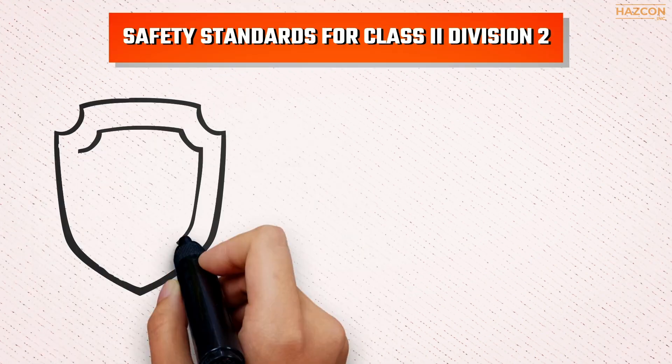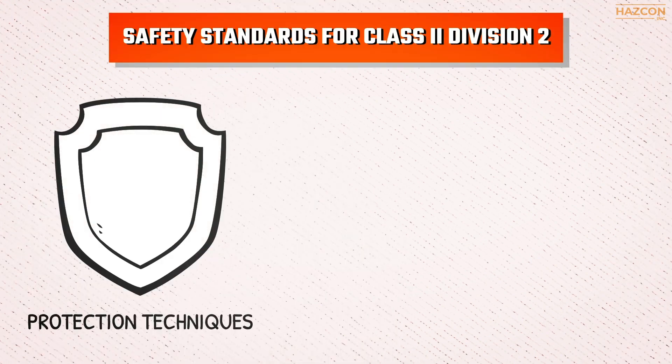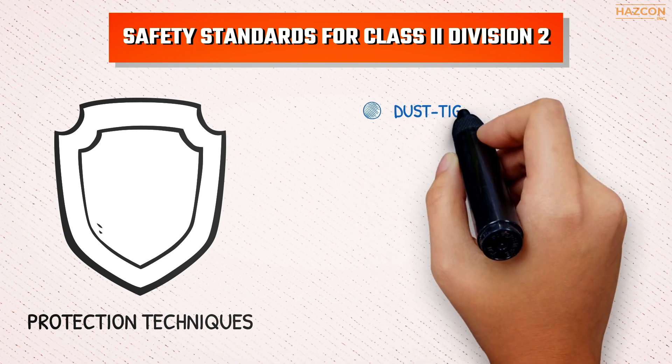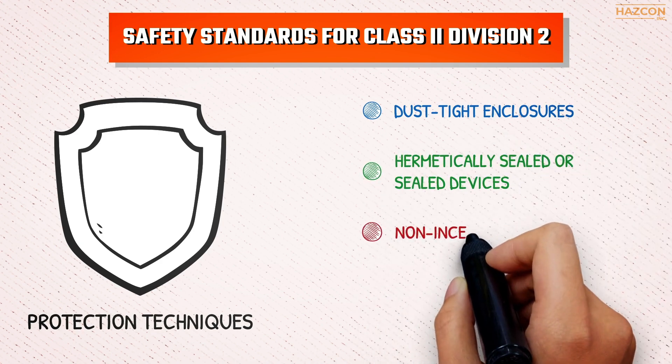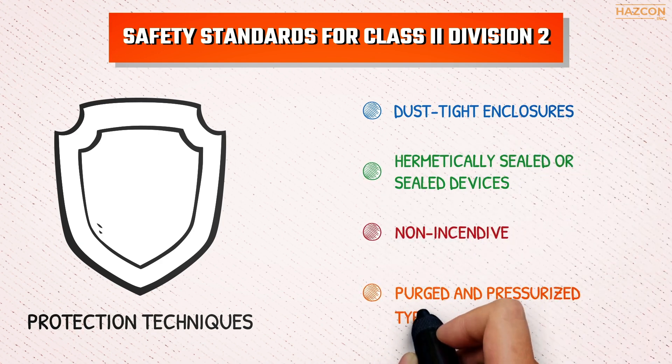In order to be certified as compliant with Class 2 Division 2, electrical products must be protected by one or more of the following protection techniques: dust-tight enclosures, hermetically sealed or sealed devices, non-incendive, and purging and pressurization Type Z.